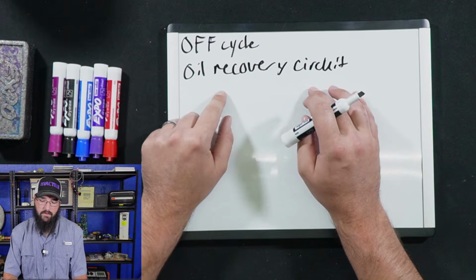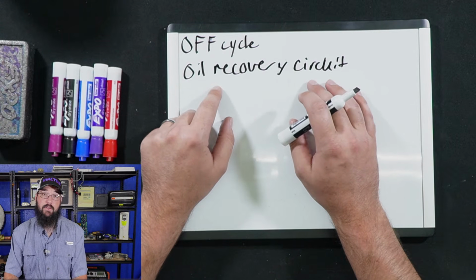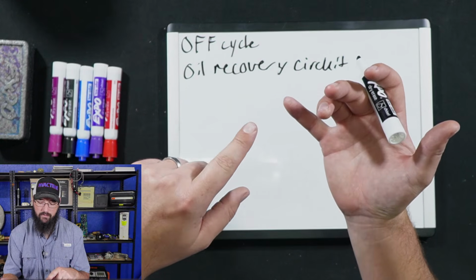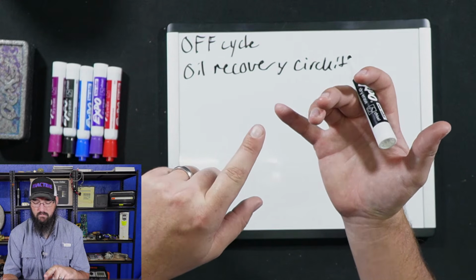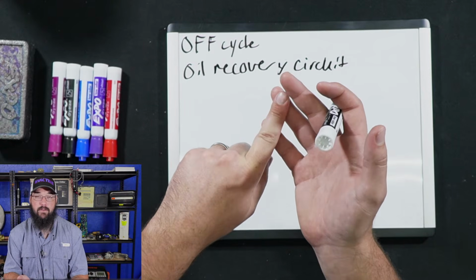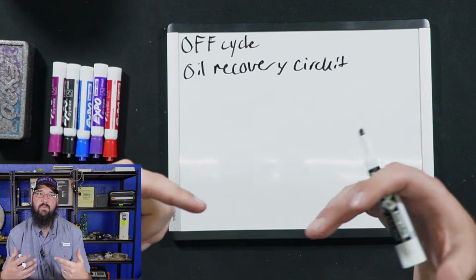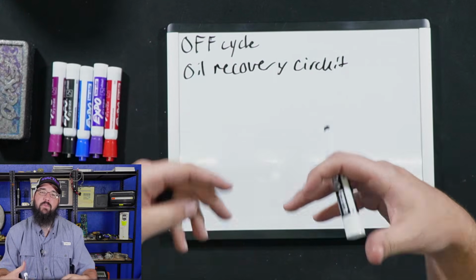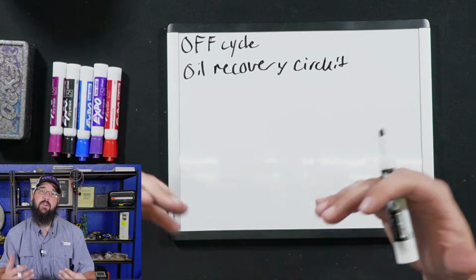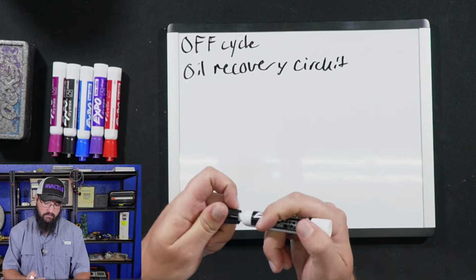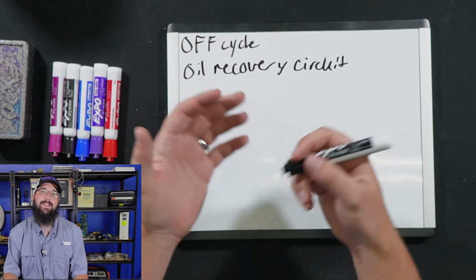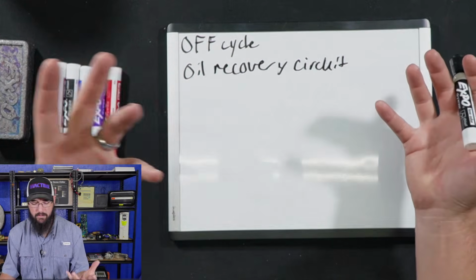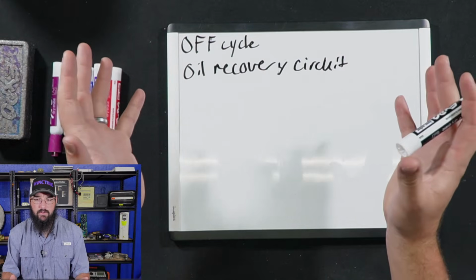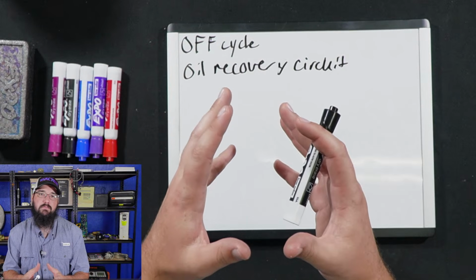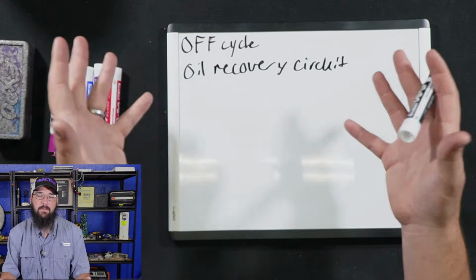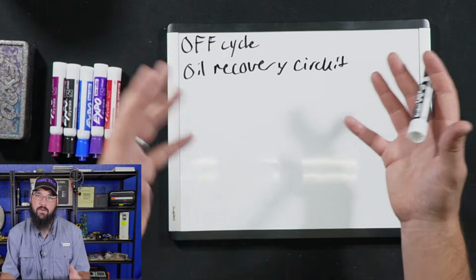If our oil circuit itself is having an oil recovery issue, so this would be an example of, we've got a flooded or falling film evaporator specifically, then those will need an oil recovery circuit in order to get that oil back. Now, the most common ways with an eductor, which you can call a jet pump, eductor, same thing. It's just two ways of saying the same thing. It's got multiple names, kind of like IGBT versus an inverter, yada, yada, yada.